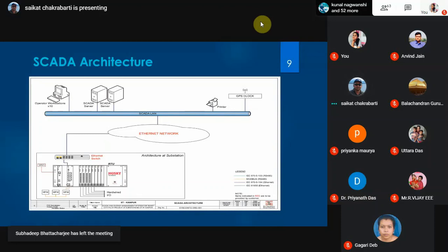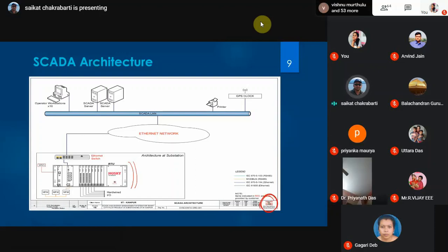What you see here is a very standard SCADA architecture that you find in a standard utility. This is the RTU, and our SCADA vendor was Synergy. This is an Indian vendor, and the RTU, remote terminal unit, is indigenously developed. You see these blocks over here, they are multifunction meters or transducers. These transducers measure voltage, current, power factor, etc., or sense the status of circuit breakers, whether on or off. And these statuses are sent to the RTU through Modbus.